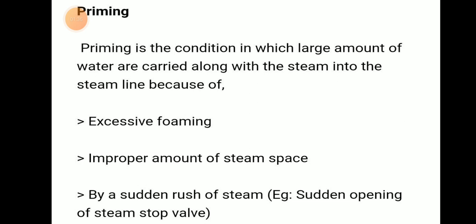Priming is the condition in which a large amount of water is carried along with steam into the steam line. This is mainly due to excessive foaming, improper amount of steam space, sudden rush of steam demand, or sudden opening of the steam stop valve.